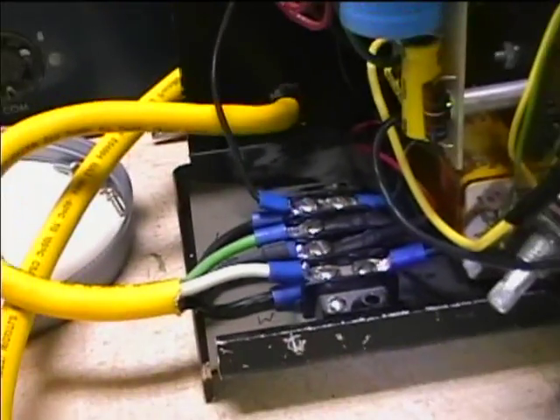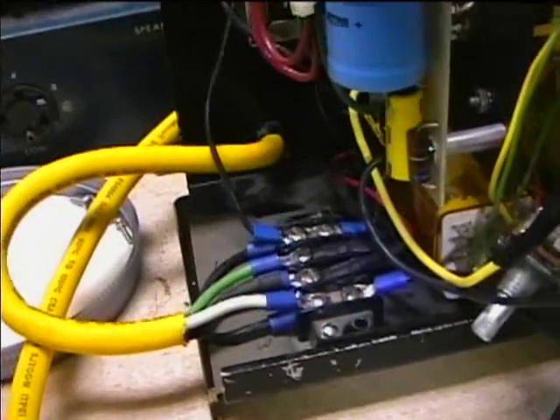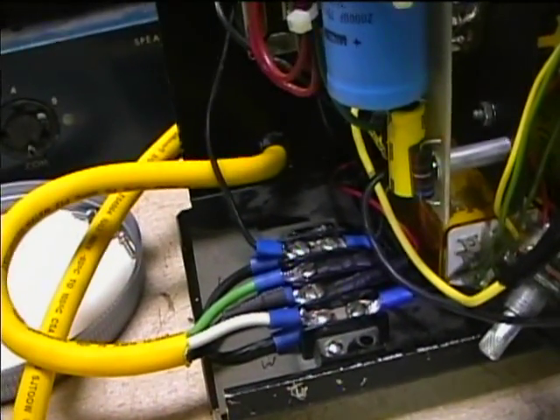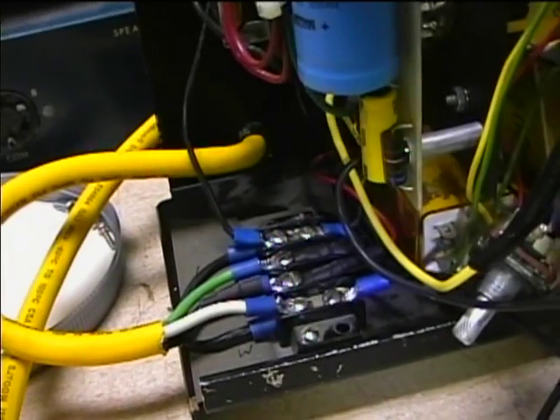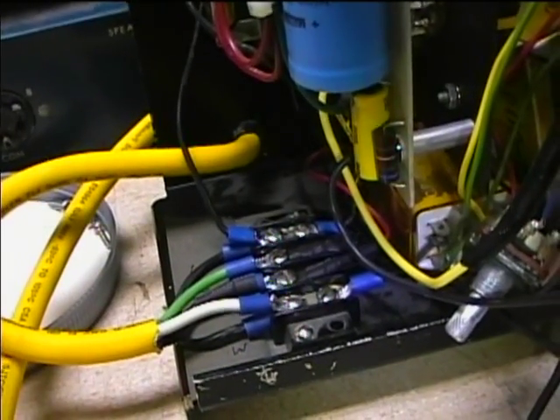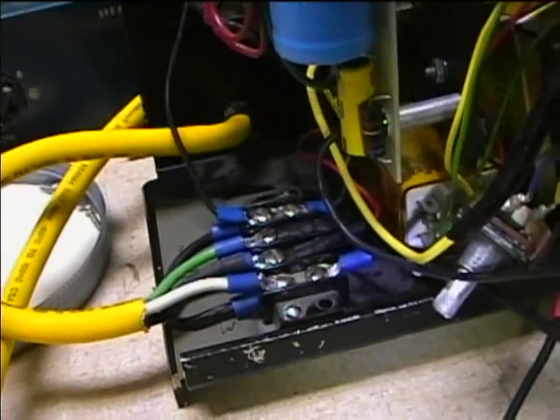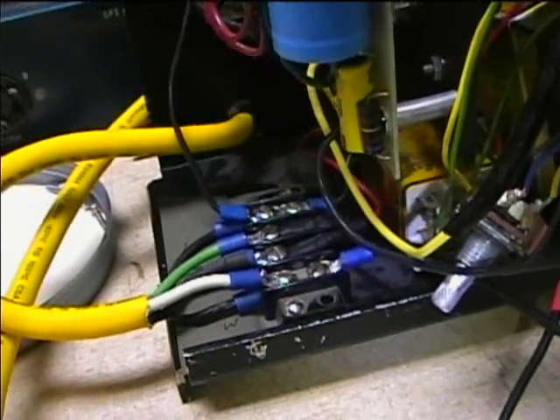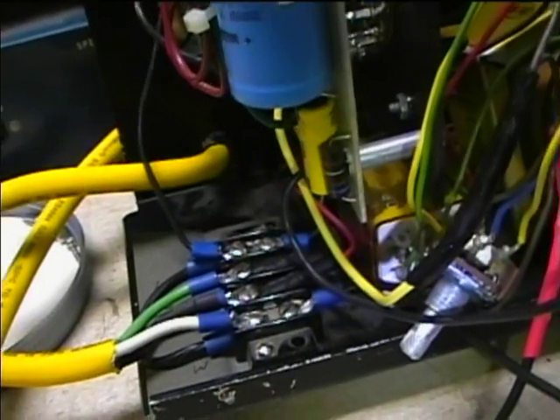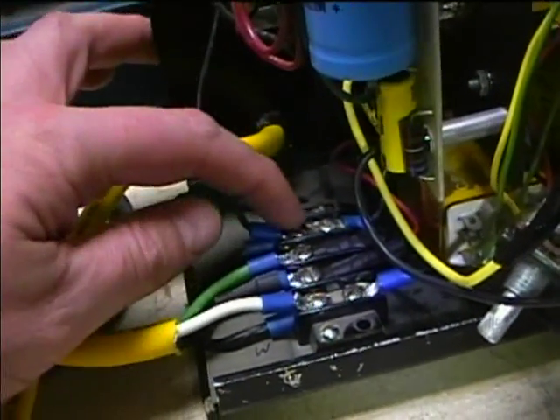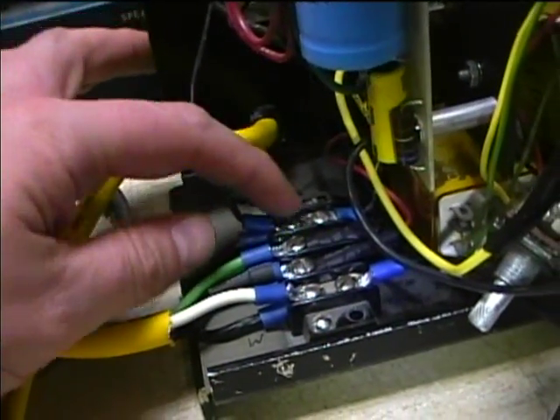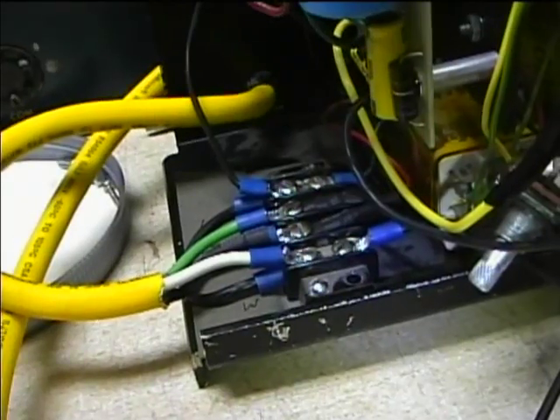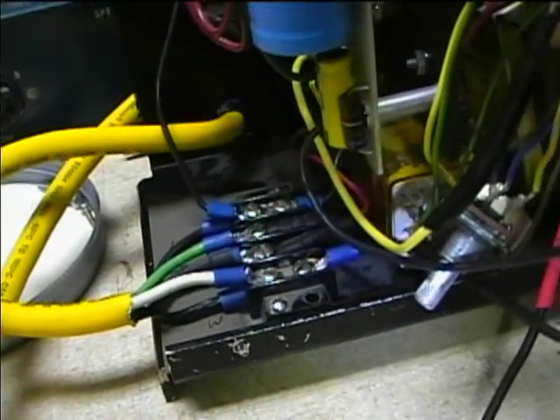I got ring terminals and completely redid the power wiring so that there's not like three terminals on one screw, with the terminal lugs trying to come up out of there. They just kind of crammed those in there before.